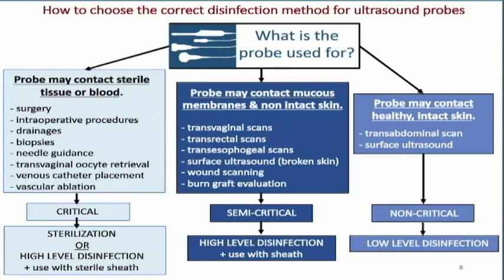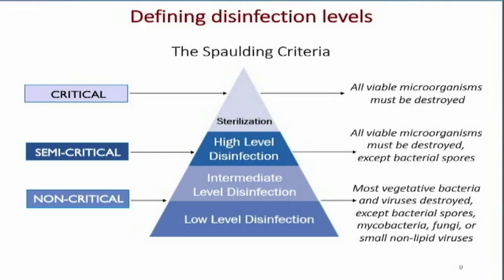These disinfection levels are based on what's called the Spaulding criteria. The critical level — intraoperative scanning — requires pure sterilization; all viable microorganisms must be destroyed. High-level disinfection, for intracavitary transducers, requires all viable microorganisms to be destroyed except certain bacterial spores. The non-critical level — surface transducers — requires most vegetative bacteria and viruses destroyed, except bacterial spores, mycobacteria, fungi, or small non-lipid viruses.